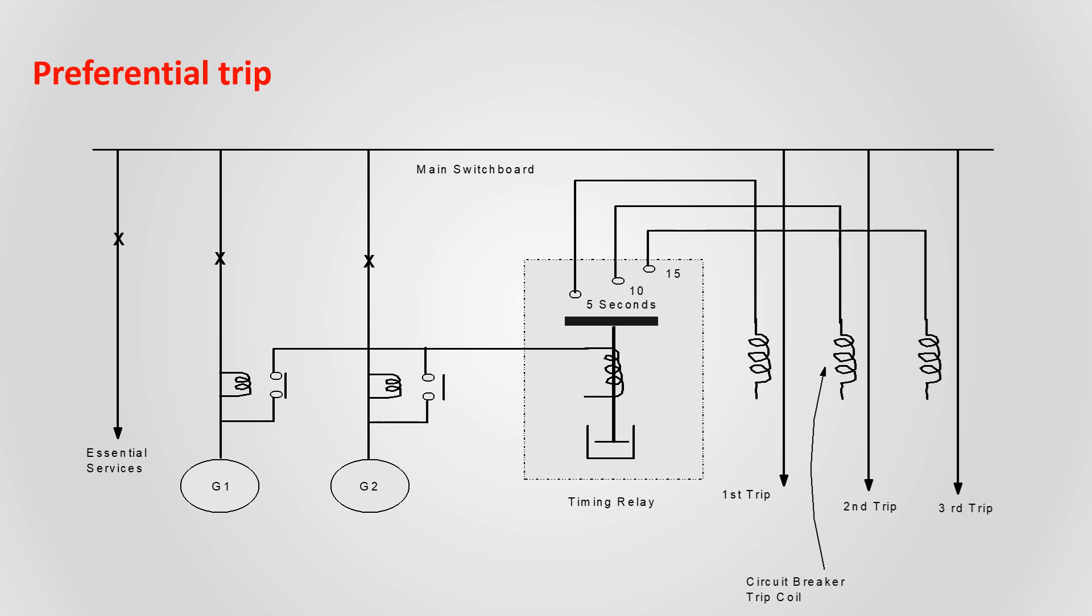If you want to test the whole system, we would use primary current injection method, or if you want to test the timing relay, we would use secondary current injection method. This test should be done by technician from shore and they have a separate kit or device for testing this preferential trip.